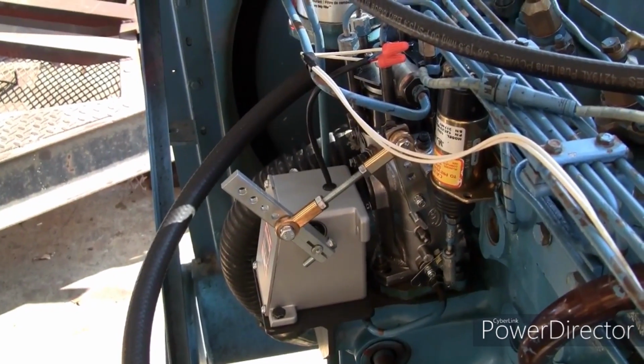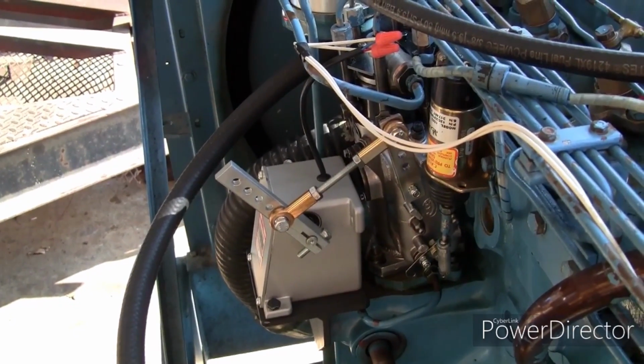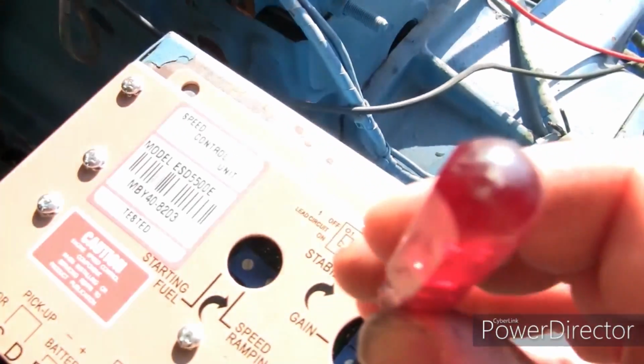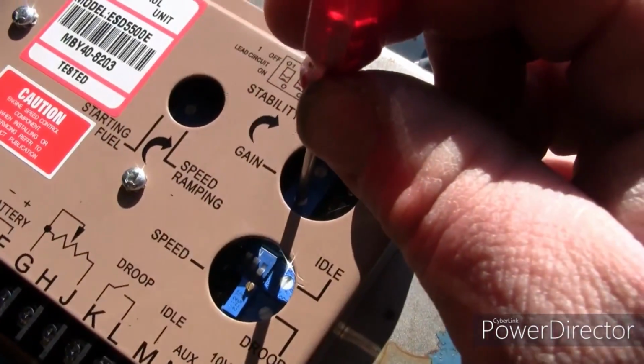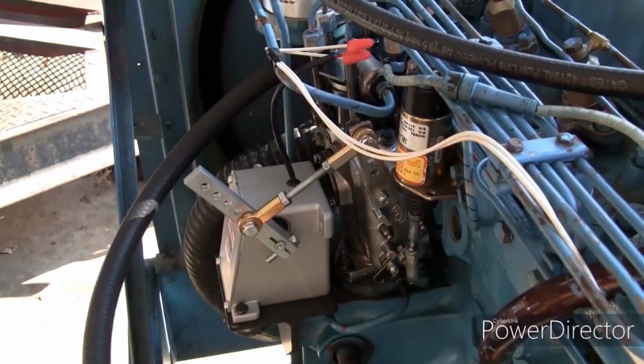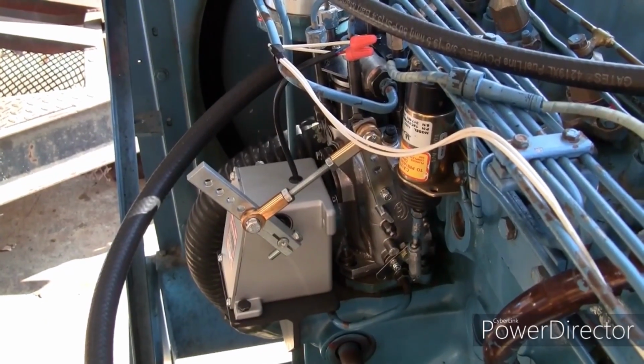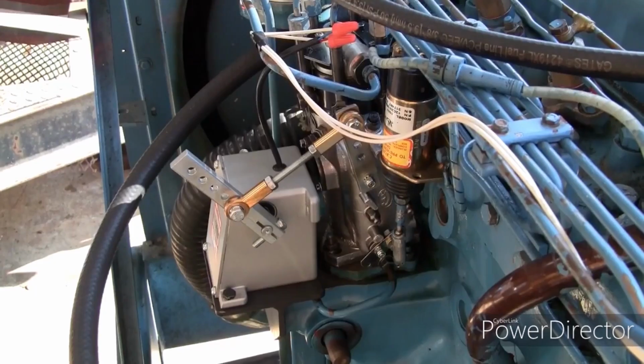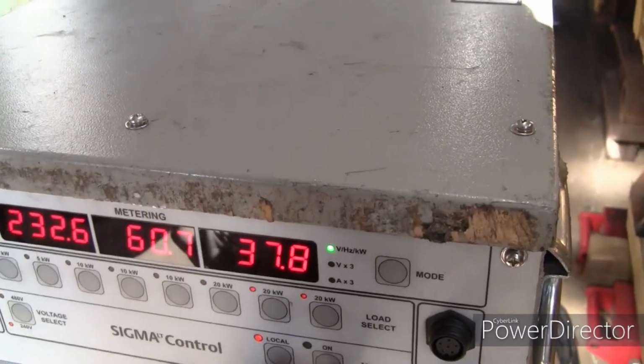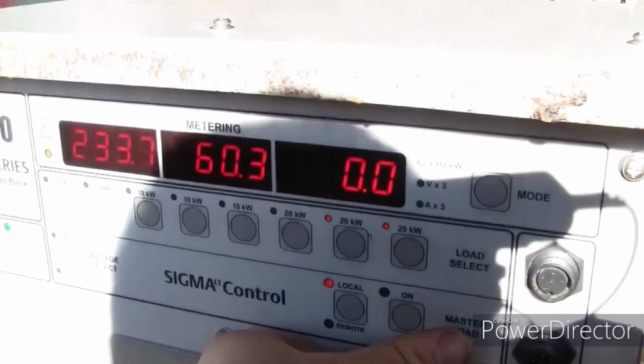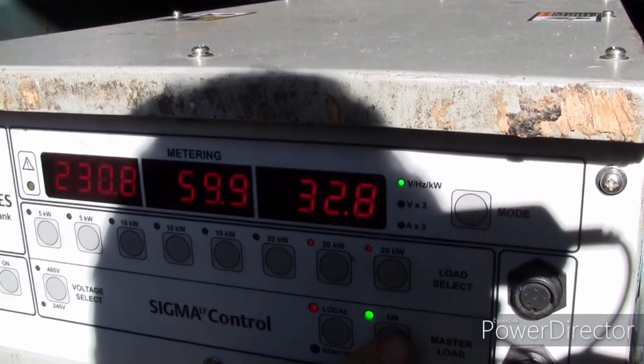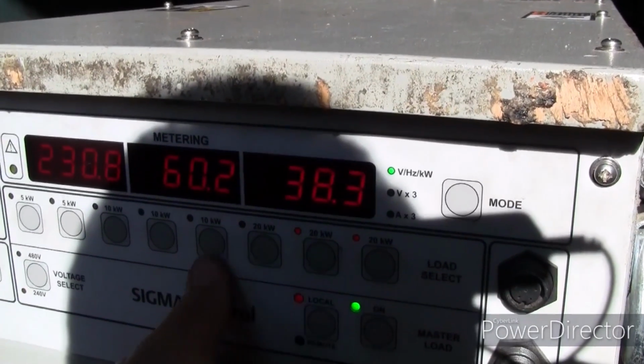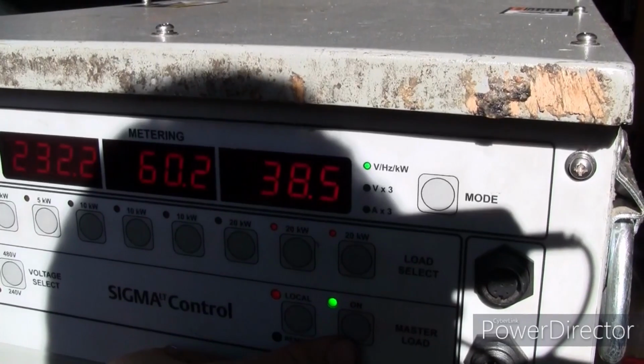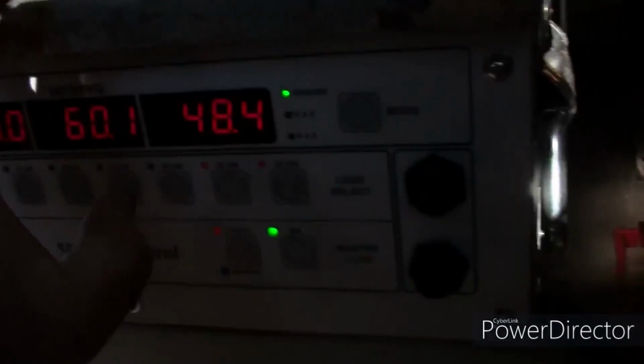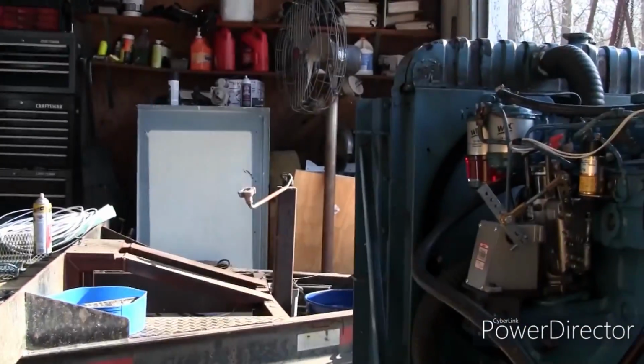So I'm turning the stability up a little bit too far, and that's adversely affecting the response of the governor at no load. Same thing with the gain. I'll bring the gain up a little bit more. We're getting that little bit of hunting or hesitation there under no load conditions. No load. Oh, what's that? That's about 40 kilowatt. The fact that the voltage is all over the place isn't helping, but that will be corrected once we replace the voltage regulator.